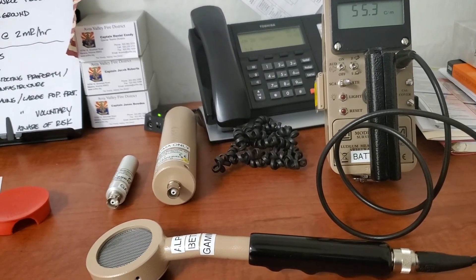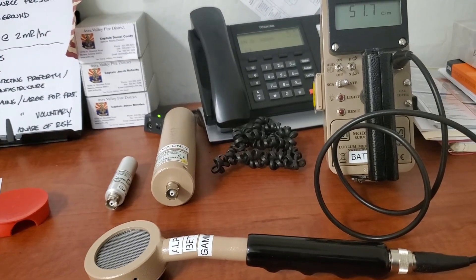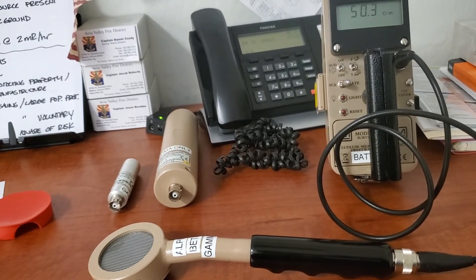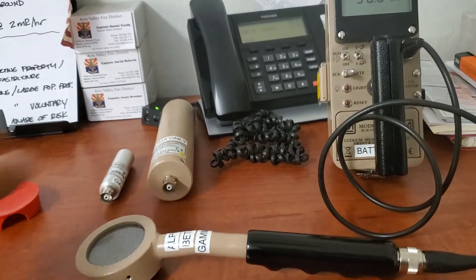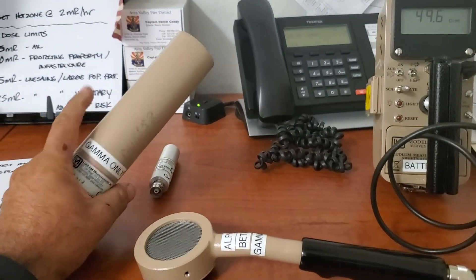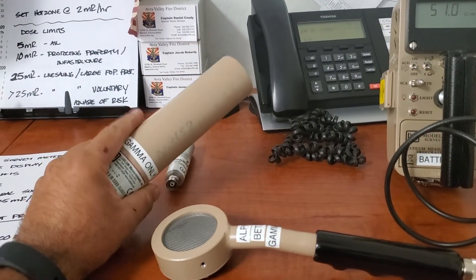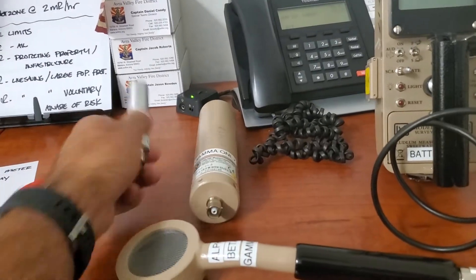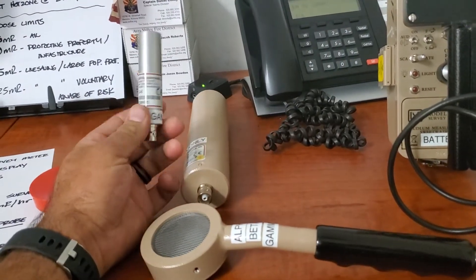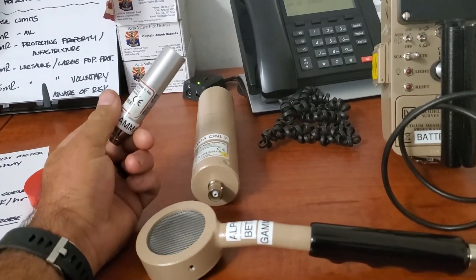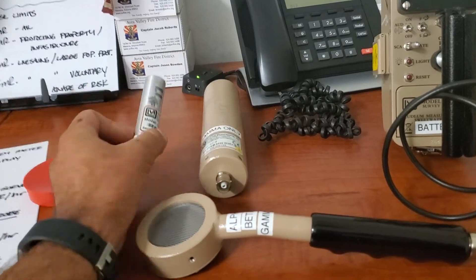We set our hot zones at 2 mR per hour. So with 2 mR per hour, we'll definitely be using this guy, because this goes from 1 micro R to 25 milli R. This one starts at 150 milli R. You'll be way past the hot zone if you decide to use this one.